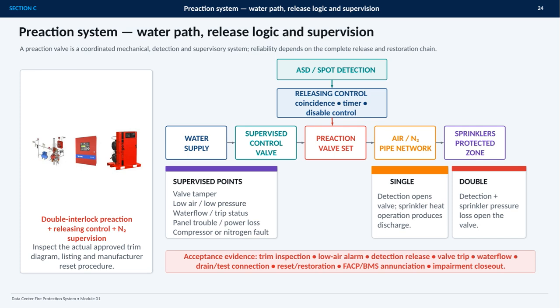Reliability depends on every link in that chain. Supervised points include valve tamper, low air or pressure, water flow and trip status, panel trouble or power loss, and compressor or nitrogen faults. Acceptance evidence should demonstrate the full sequence.